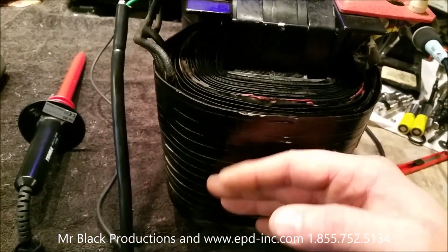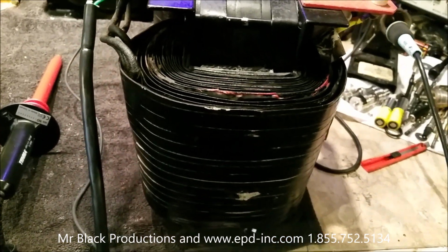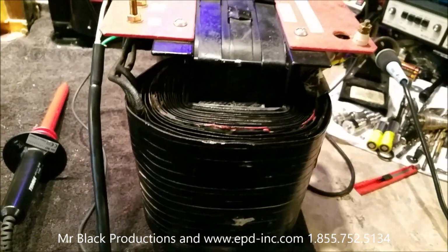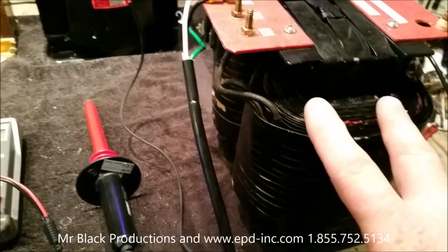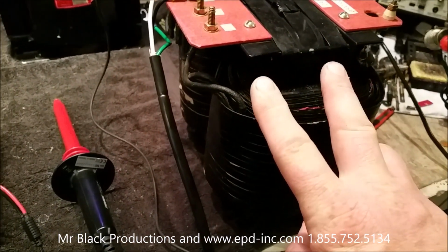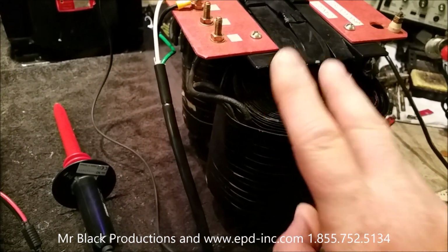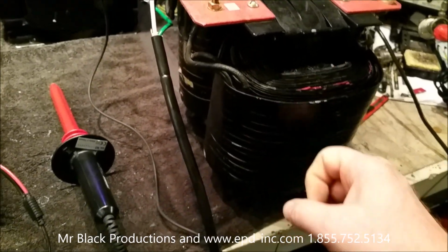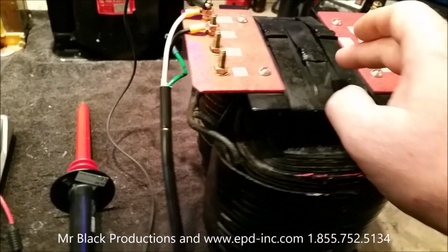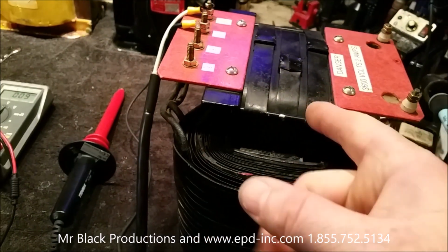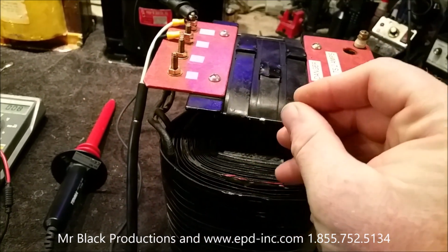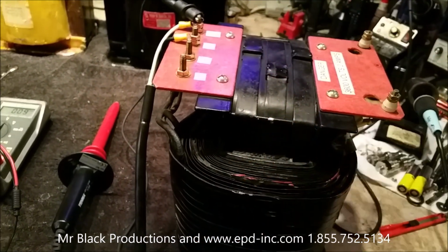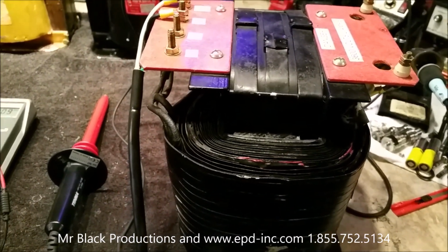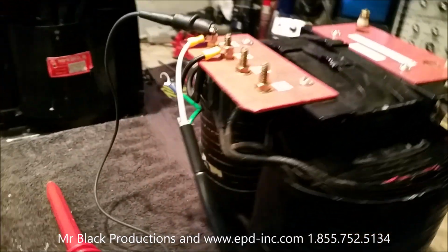These coils have been beat around so much that the wrap inside of them is now a little loose. The things that will make a transformer hum: one, poor design; two, your windings are loose; and three, the plates that make up your core have delaminated or don't have enough pressure on them to hold them together. Everything here makes a difference.